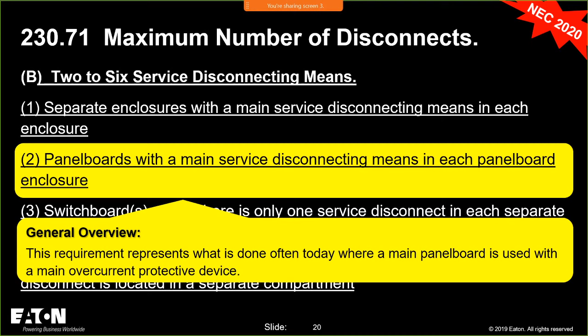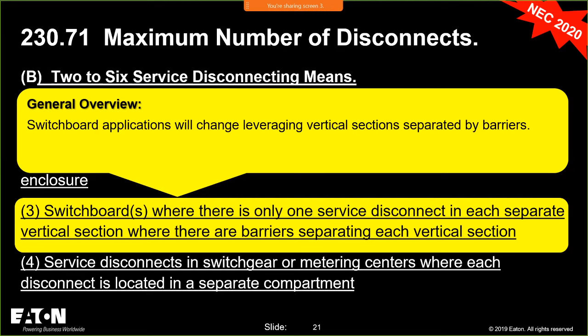The third option, they lumped switchboards. So this is switchboards. This is saying that each service disconnect has to be in its own vertical section where there are barriers separating each vertical section. So again, this is probably more of a change that's going to impact manufacturers to provide these solutions. But I believe these are readily available to date. And when you put the main service disconnect in each vertical section, you'll be able to barrier off that line side terminal, which makes meeting the barrier requirements easier as well.